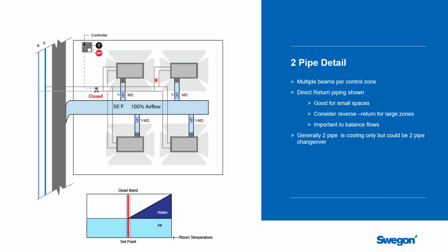Now the way we've drawn this piping in here is direct return. Reverse return is fine. It really is going to depend on how the beams are laid out and how you can run it. Nice thing about reverse return piping is it means that all the flows will be balanced and that the system will self-balance and deliver the same amount of flow to all these beams. In a small system, direct return shouldn't make a big difference. In a larger area, I would probably recommend that you look at reverse return piping.